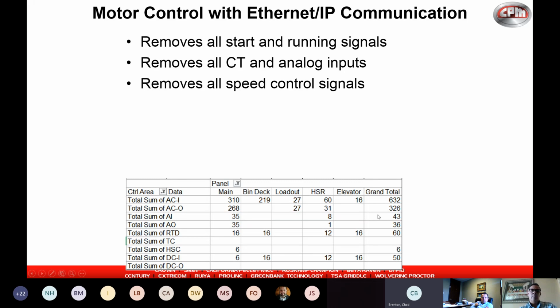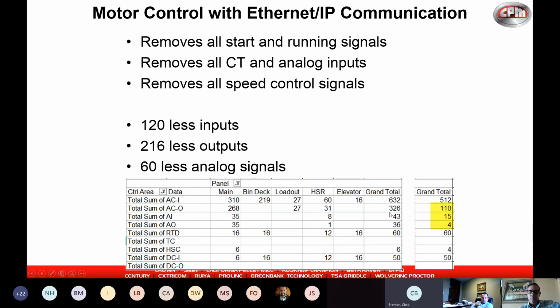This was the IO total from a brand new facility we worked on a couple years ago, before they went to a smart MCC. I want to highlight the outputs, analog inputs, and analog outputs: when they went to a smart MCC, it went down by 120 fewer inputs, 216 fewer outputs, and 60 fewer analog signals just by going to a communication protocol on all the motors. That's a lot less work for electricians, more room in the MCC room with less conduit, and less IO hardware we have to provide.